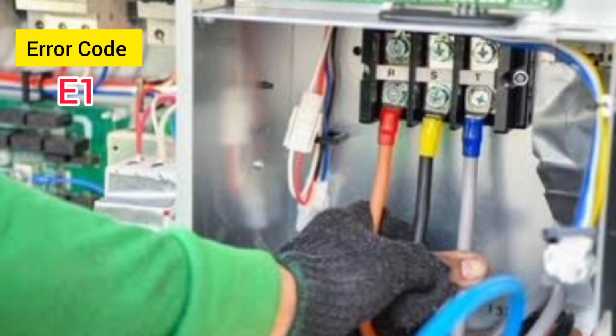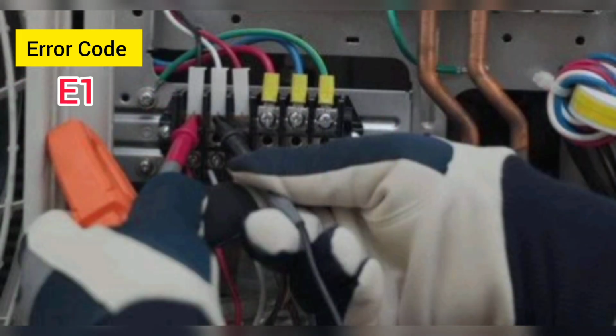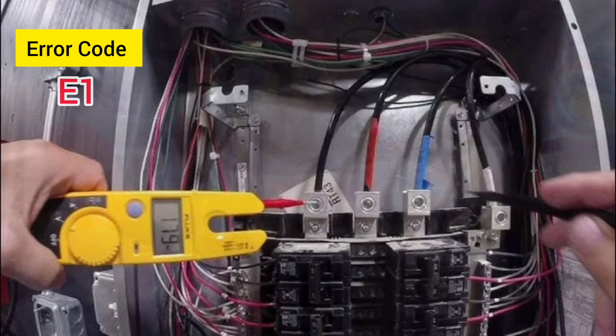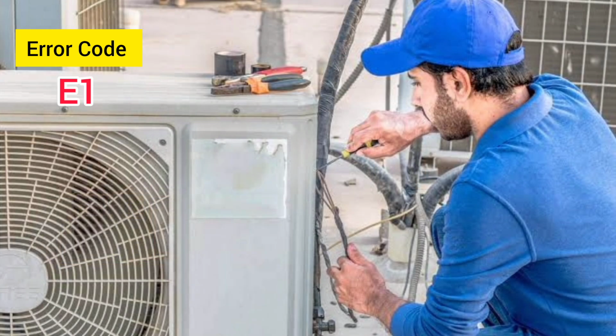Number 2. Check wiring. Carefully inspect all wiring connections between the indoor and outdoor units for loose or damaged wires. Ensure all connections are tight and secure. If you find any problem, repair or replace the wiring as needed.